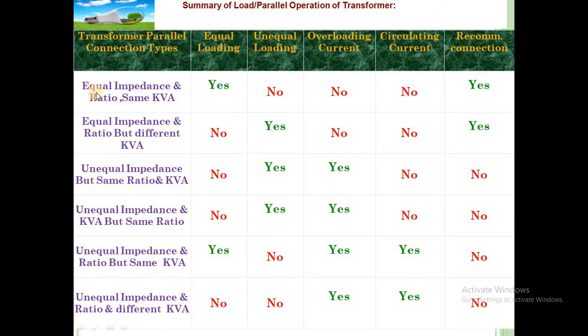So first we'll see equal impedance and ratio, that is impedance ratio, same kVA rating. So हे सगळं जर इक्वल असेल, सेम केव्हीए रेटिंग असेल, दोन ट्रान्सफॉर्मर जर आपण पॅरललमध्ये कनेक्ट करू तर दोन्ही ट्रान्सफॉर्मरचे इम्पिडन्स इक्वल असेल, रेशो सेम असेल, केव्हीए सेम असेल, then equal loading, yes there will be equal loading. Obviously unequal loading will not be there, overloading current will not be there, circulating current will not be there, and yes it is a recommended connection. So this connection is recommended.